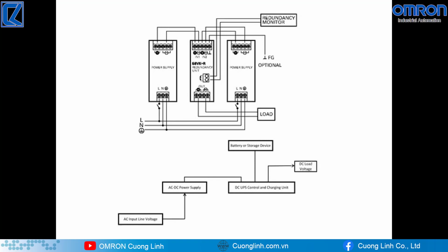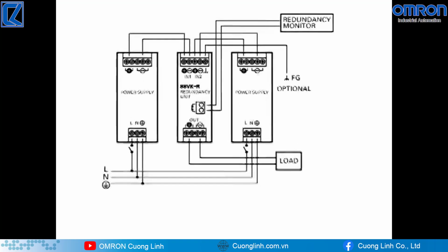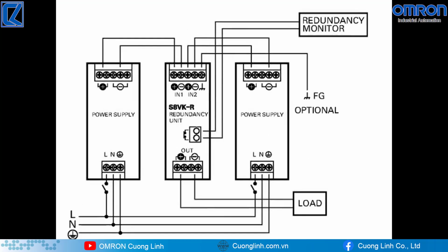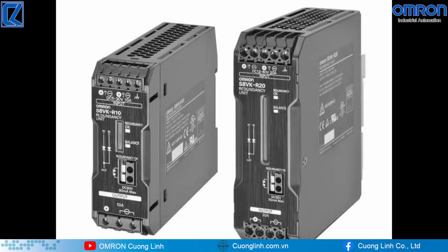applications. The redundant power supply system consists of two similarly sized AC to DC power supplies, installed along with a diode system to prevent feedback to connected power supplies. This system is wired in a way to allow both power supplies to provide DC voltage to the same load. The OMRON redundancy units, S8VK-R10 and the S8VK-R20, contain the diode system and detection circuit to monitor the status of both power supplies.